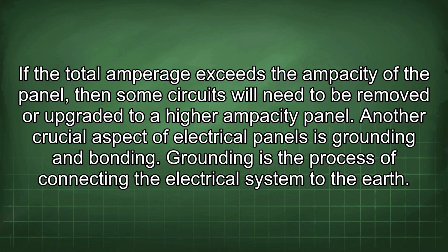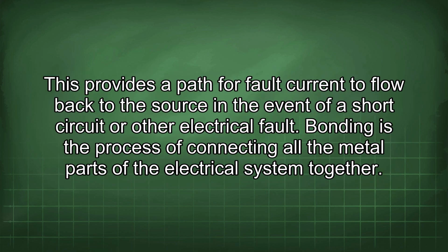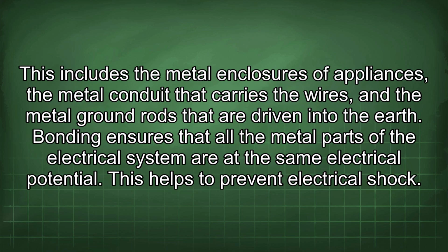Another crucial aspect of electrical panels is grounding and bonding. Grounding is the process of connecting the electrical system to the earth. This provides a path for fault current to flow back to the source in the event of a short circuit or other electrical fault. Bonding is the process of connecting all the metal parts of the electrical system together. This includes the metal enclosures of appliances, the metal conduit that carries the wires, and the metal ground rods that are driven into the earth. Bonding ensures that all the metal parts of the electrical system are at the same electrical potential. This helps to prevent electrical shock.